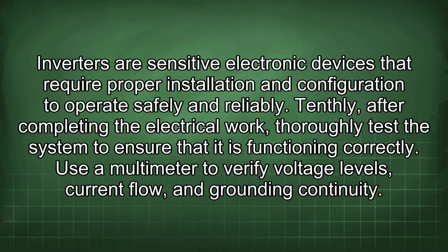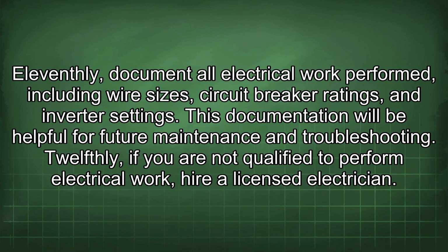Tenthly, after completing the electrical work, thoroughly test the system to ensure that it is functioning correctly. Use a multimeter to verify voltage levels, current flow, and grounding continuity. Eleventhly, document all electrical work performed, including wire sizes, circuit breaker ratings, and inverter settings. This documentation will be helpful for future maintenance and troubleshooting.